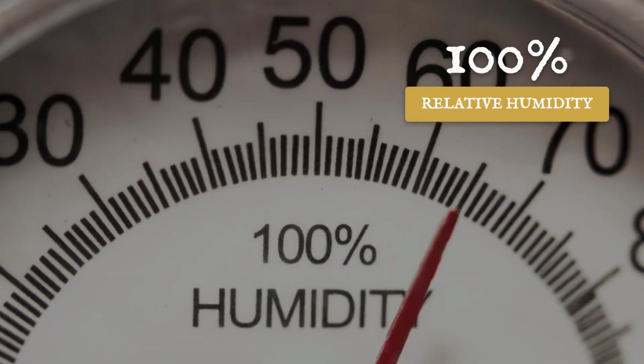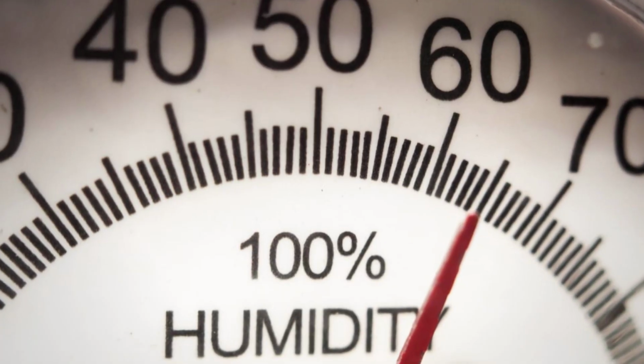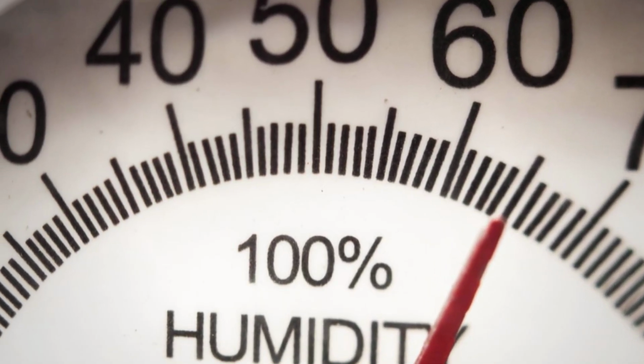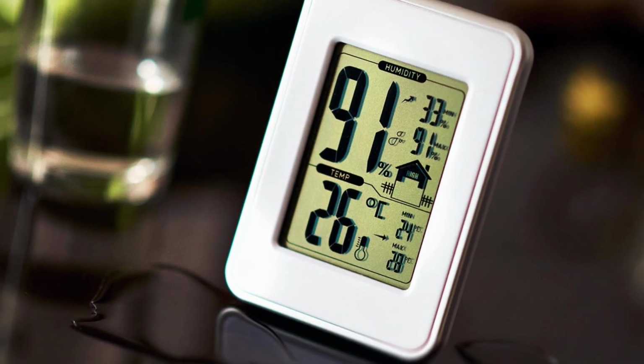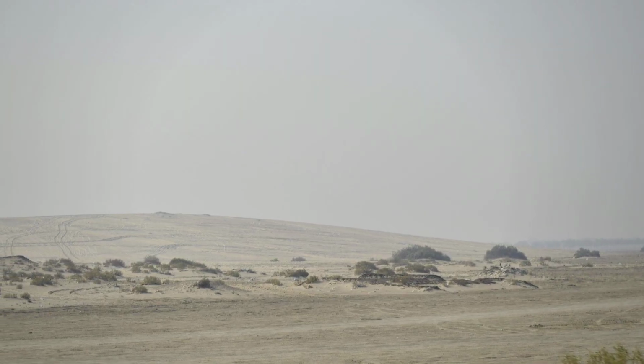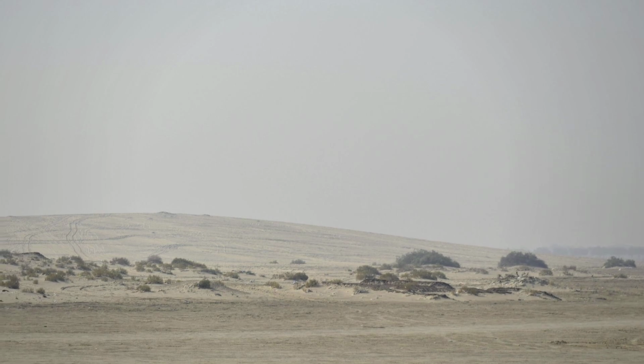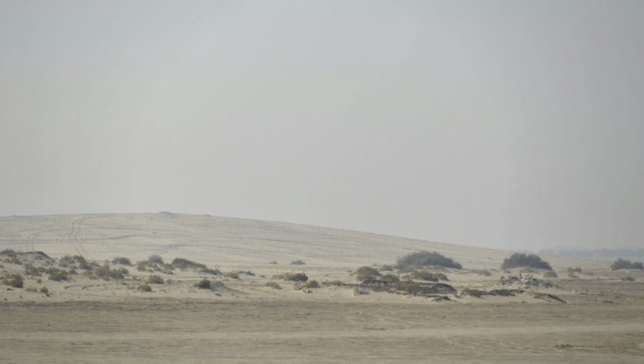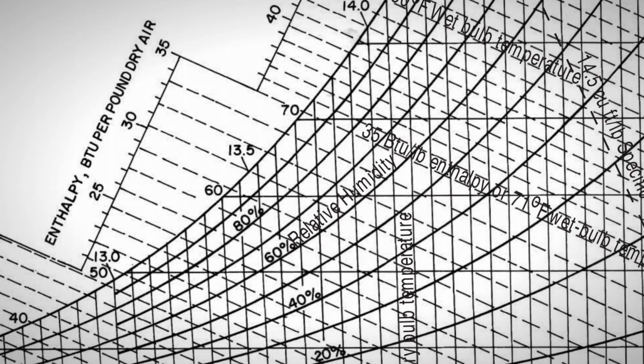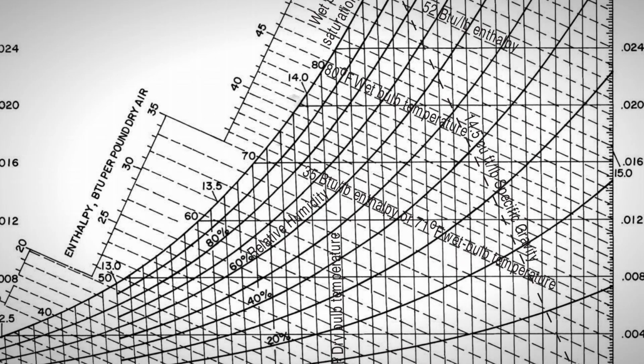Consequently, as long as the ambient air isn't completely saturated, 100% relative humidity, water can be cooled below the dry bulb temperature through evaporation. The lower the air's humidity, the greater the evaporation, and thus the greater the cooling potential. While evaporative cooling is a natural phenomenon, evident in how our bodies sweat to regulate temperature, its application at this industrial scale is truly remarkable. And it's not the only innovation in a natural draft cooling tower.